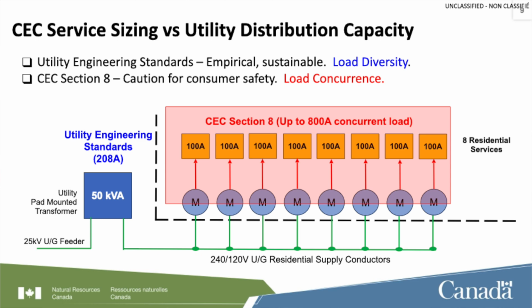We do this at development. If you're going into an existing area as a retrofit, of course the developer at the time assumed everything was going to be 100 amp service. Now you're adding a 200 amp because you've got a net zero home being built, or something with a huge electrical load. All of a sudden that transformer has to be adjusted because somebody else before you added some other electrical devices. You don't want to be the first person to pay for it.